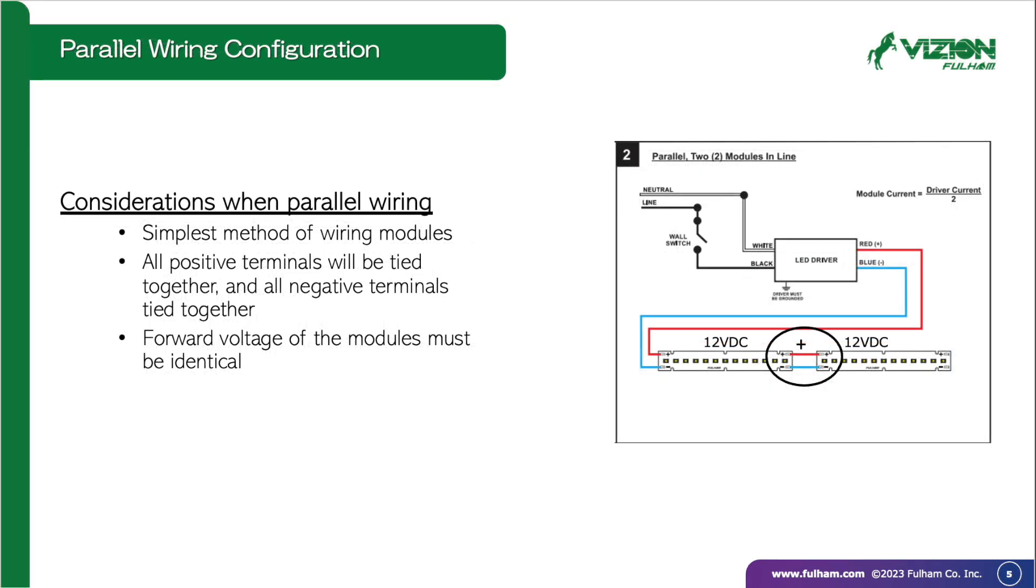Parallel wiring configurations are the simplest form of wiring, since all positive terminals and all negative terminals of the modules and drivers will be tied together. In this wiring configuration, voltage must be identical in the modules to ensure proper current distribution amongst them.